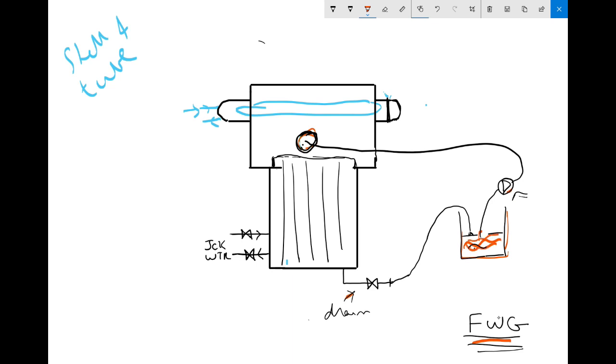Normally if you are using Drew Marine company chemical, then you will have safe acid. You can use that safe acid, and you can refer to the manual. It depends on the quantity of water which you are using. If you are using a particular quantity, then you will have to use a particular amount of acid. For safe acid, after you mix the chemical, the color of the chemical should be international orange. That is the reason I have selected the orange color.